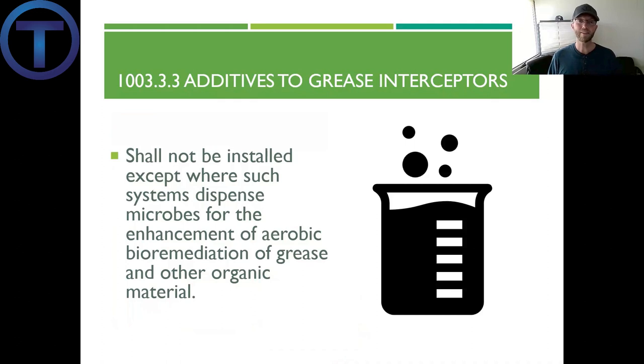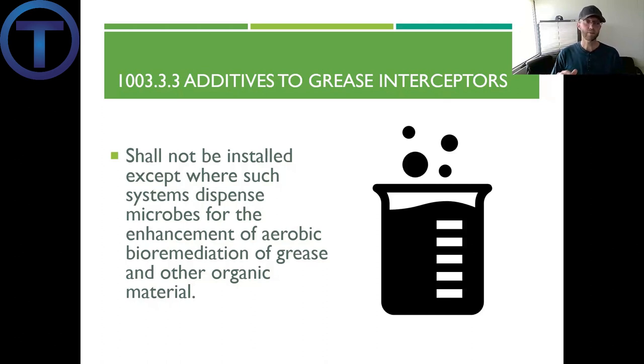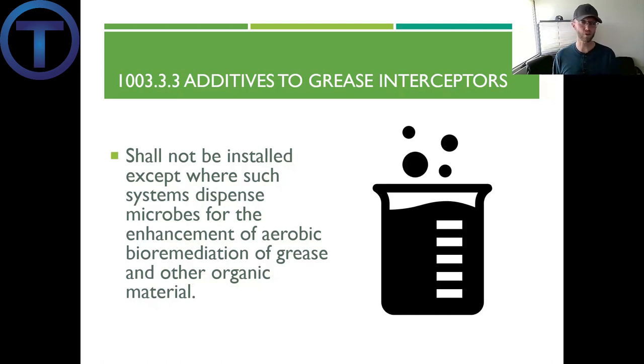With a gravity-type grease interceptor, there are some products that may be used to help performance, but when it comes to additives, Section 1003.3.3 states they shall not be installed except where such a system dispenses microbes for the enhancement of aerobic bioremediation of grease and other organic material. Basically, if you're putting chemicals in there that are killing what's in there, it may not work as well.